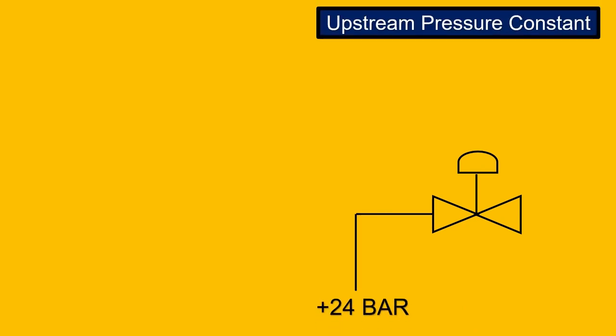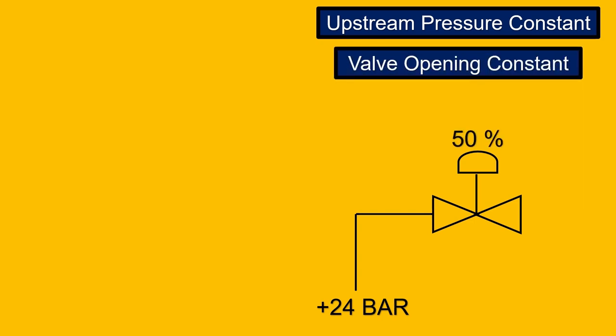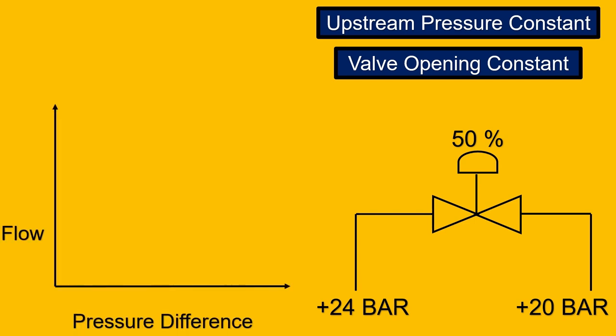Now, if you have to understand this concept we can say that if we have a valve and we keep the upstream pressure is 24 bar so we keep a constant upstream pressure and the valve opening is kept constant. For example, let's say 50 percentage and we keep increasing or decreasing the downstream pressure like example 20 bar, 19 bar, 18 bar and we try to plot a graph we will be getting a linear characteristics.